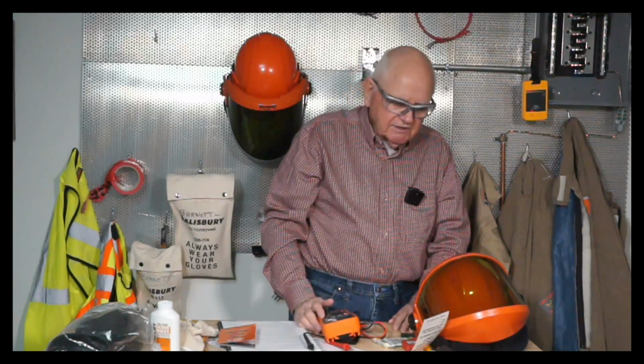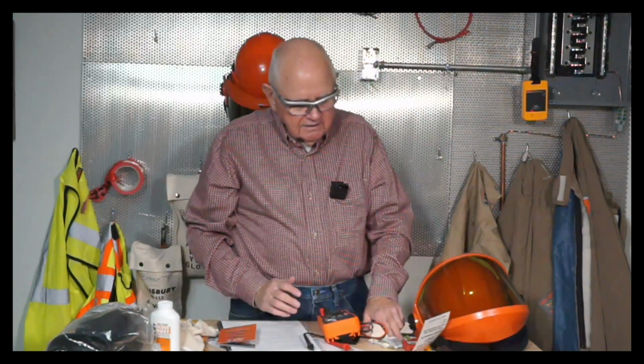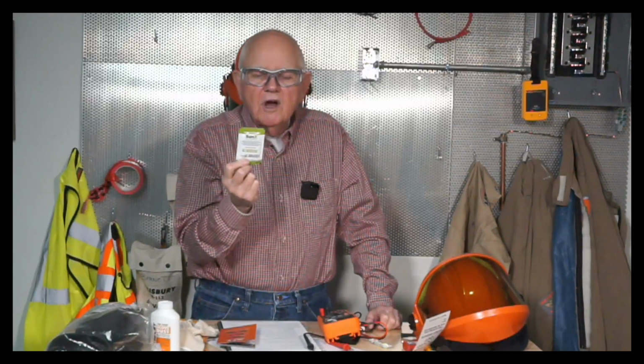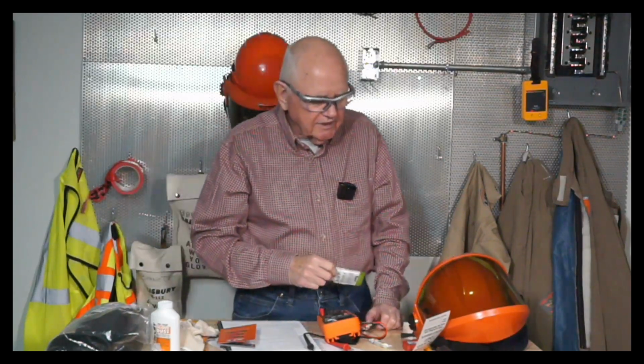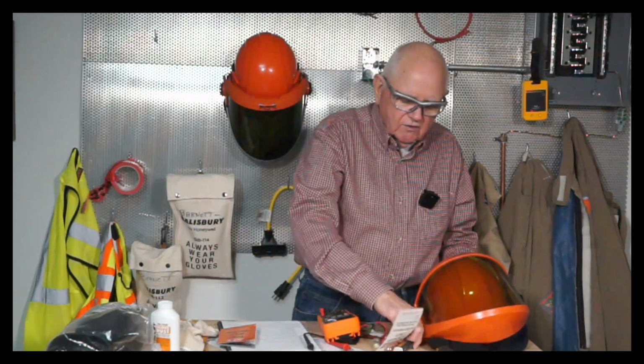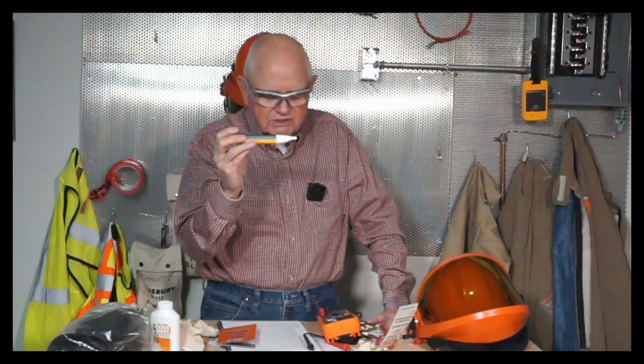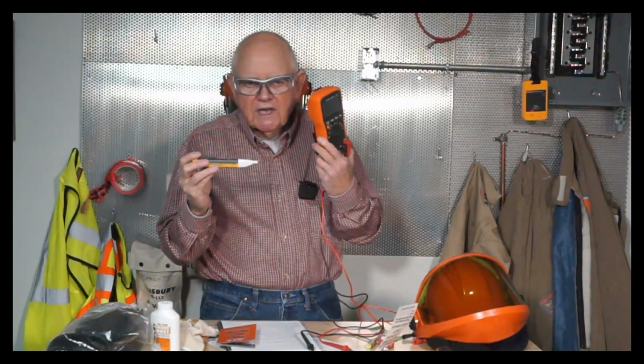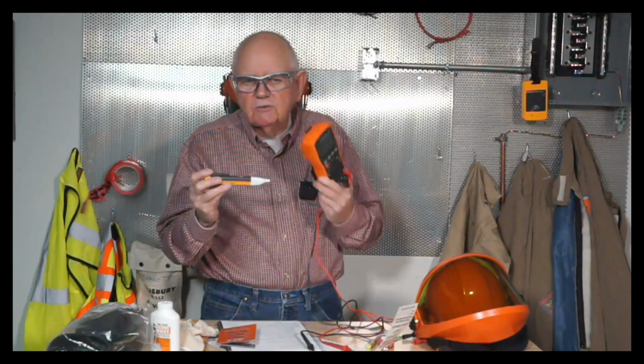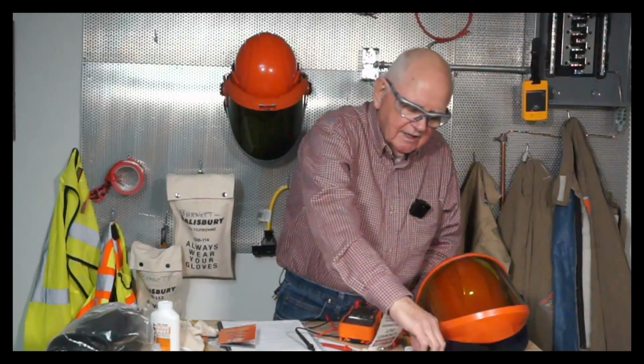A couple other things on PPE then. Here's some sunscreen. This sunscreen will not deteriorate the properties of my flame-resistant garment. I can buy the same when it comes to insect repellent. So consider that if you're using any of that out in the field. Test equipment. Capacitive voltage testers like this, non-contact devices: for verification of voltage at less than 1000 volts, I need to use the contact instrument. Above 1000 volts, I can use my non-contact voltage detectors. Follow your procedures once again.